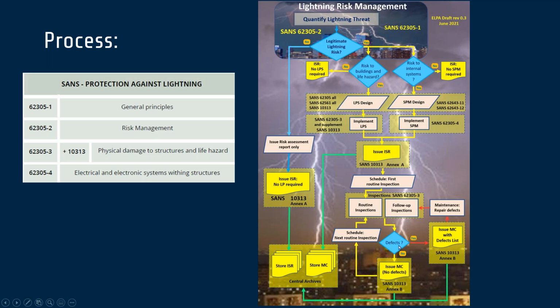The outcome of the inspection shows that there are defects. The defects need to be listed. The SANS 10313 maintenance certificate must still be issued - this is where it differs from an electrical COC. A maintenance certificate for lightning protection must still be issued.